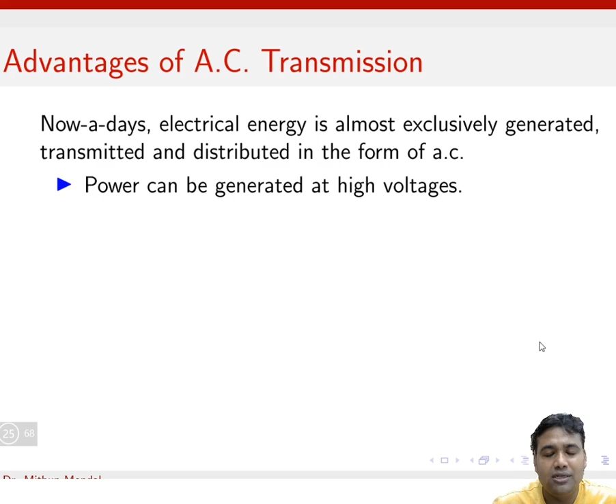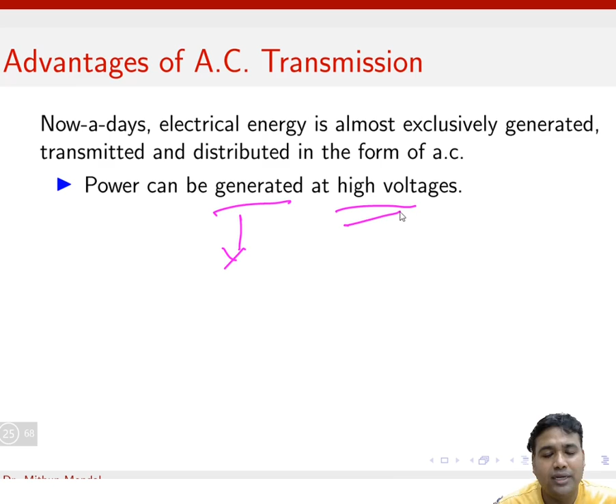Power can be generated at a high voltage. This is the big advantage of AC, because you have a transformer and a synchronous generator, which both operate with AC supply. So power generation is done at high voltage with the help of alternators. The maintenance of AC substations is easy and cheaper as compared to DC substations. The AC voltage can be stepped up or stepped down with a transformer with ease and efficiency. This is a great advantage for the AC supply, which can't be had in case of DC.